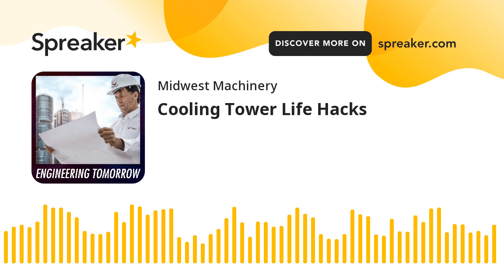If that direct drive fails, then you're kind of in trouble. The other thing to consider is, my understanding of how these work is that you have to have the VFD connected for the direct drive motor to run. So if your VFD goes down, you don't have the ability to run the direct drive in bypass mode like you would with a standard motor and gearbox. So there's an extra fail point without a plan B if the VFD goes down and you've gone with a direct drive. Just some things to consider.